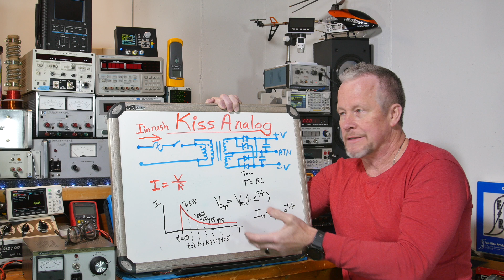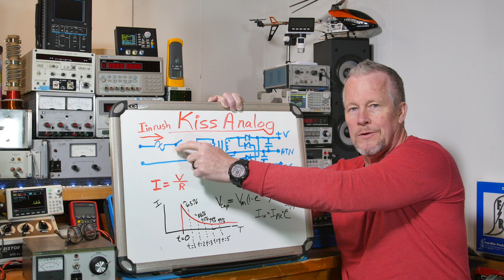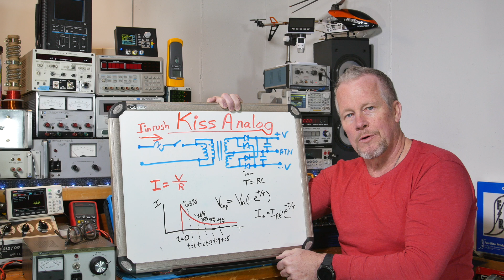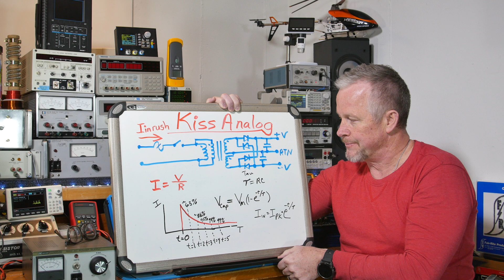It's common, if you're doing this method, to try it 20 times. After the first few times, you'll start to see a common value, and you'll be able to tell from the look of the waveform where you're getting lucky or unlucky when you hit that switch. Keep trying until you get some real high peak values, just discharging your caps in between each try.